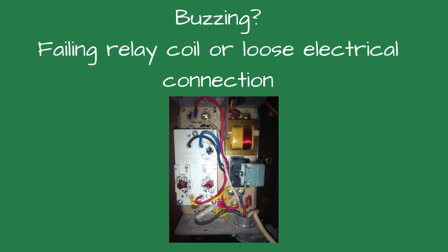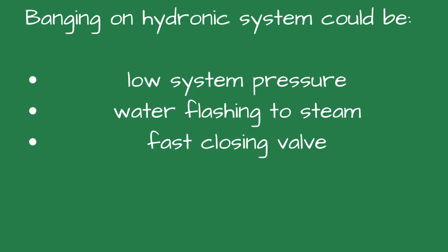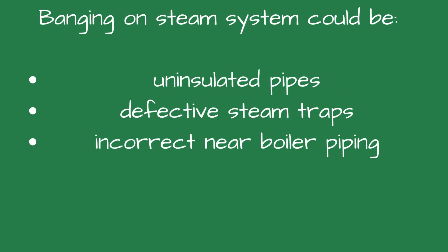Buzzing could be a failing relay coil or loose electrical connection. Banging is never normal inside a boiler room and is an audible cry for help. If it's a hydronic system, it could be low system pressure, water flashing to steam due to low flow or excess system temperature, or a fast-closing valve. On steam systems, it could be water hammer from uninsulated pipes or a defective steam trap, improper near-boiler piping, or a barometric damper.